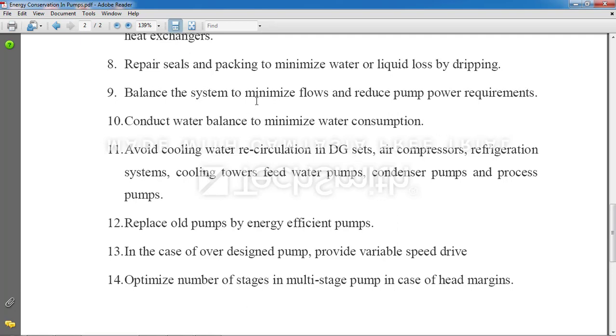Next, balance the system to minimize flows and reduce pump power requirement. This is called optimization. It means how we can reduce the size of the pump, or how we can reduce the length of pipes, because pipe length also matters a lot. If you increase the pipe length, you will have to increase the power of the pump system, because to make the water flow over a long distance you should create that much suction.